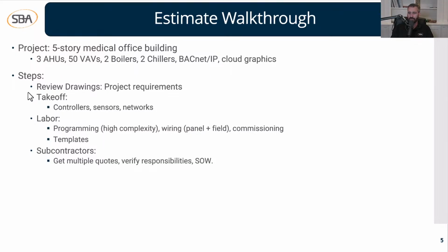Now the flow is we go through the drawings and the sequence review. We need to understand if it's just controlling the units, or if there's additional work, like integrating to the fire smoke interface. Maybe we have to BACnet into our supervisor controller from the fire control system to get an alarm and then shut down our air handlers. I've seen that a lot. Sometimes you'll also have to integrate to access control, or maybe even the lighting control system. A lot of times when working on performance agreements, you'll see lighting controls included, because that's usually the first thing they retrofit, since it's the easiest.